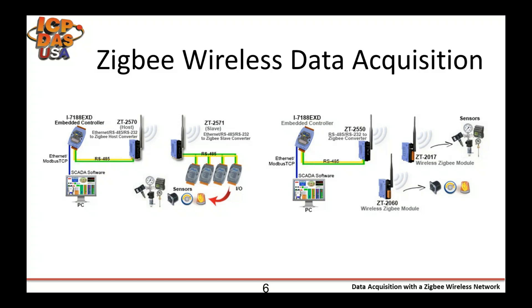We're seeing two different ways to build a data acquisition system using a ZigBee network. On the left-hand side, you can see what is essentially an RS-485 network using ZigBee as the bridge, which would be useful in situations where the extension of a wired network would be inconvenient or even dangerous. The I-7188 automation controller sends instructions to the ZT2570 ZigBee host, and the ZT2571 slave module converts the signal back to RS-485, passing instructions to a network of Modbus Remote I/O modules. On the right-hand side, we see the same process handled by ZigBee end devices — the ZT2017 and the ZT2060 — forming its own wireless network with decreased wiring and more flexibility in placement.